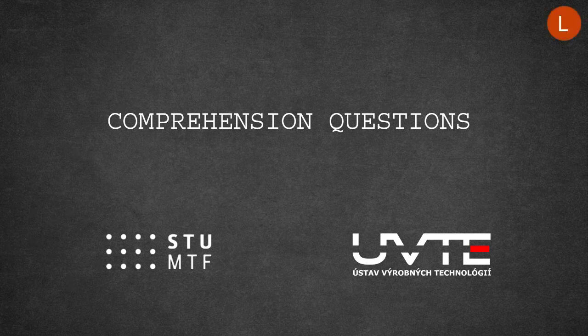Yes, it's true. And what do you think, is it possible to change, because on the video was presented a tactile sensor, so a contact method of measuring, but it's also possible to use this machine for non-contact measuring. The way to do it is to change the tactile stylus or tactile sensor to a scanning head, and this scanning head also uses an active triangulation method. This method, or the combination of this scanning head for active triangulation, also for fringe projection, is also a used method of measuring on coordinate measuring machines.